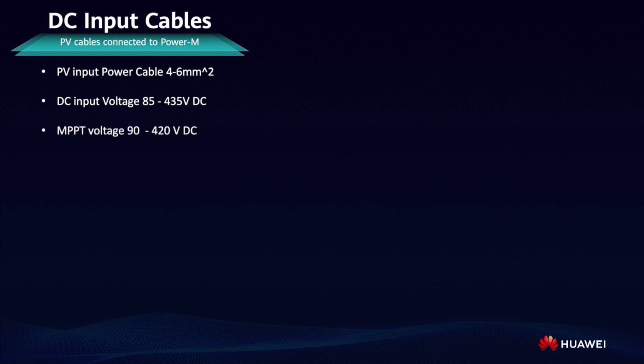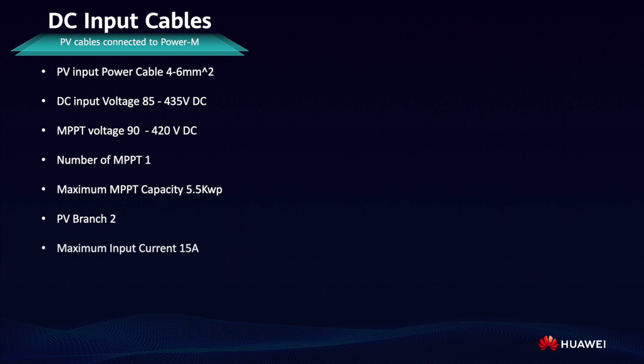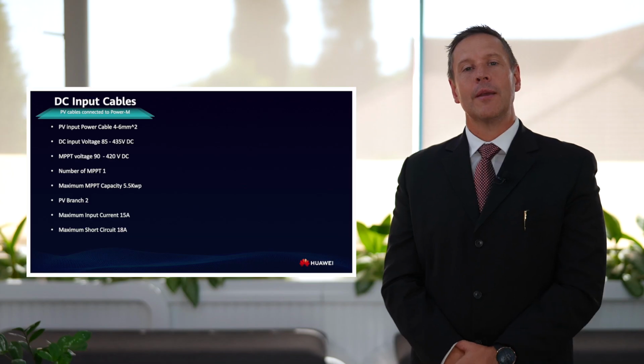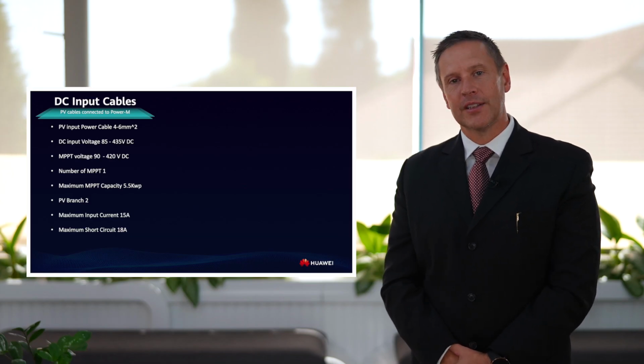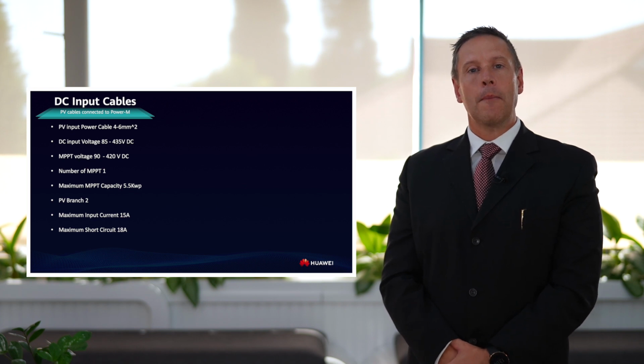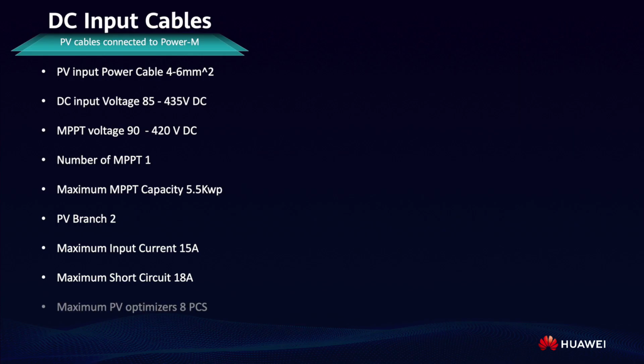MPPT voltage between 90 and 420 volt DC. There's one MPPT on the inverter itself. The maximum MPPT capacity of 5.5 kilowatt must be adhered to. There are 2 PV branches and the maximum input current is 15 amp into each branch, therefore allowing up to 30 amp in the combined configuration. The maximum short circuit is 18 amps. The Power M is also capable of accepting optimizers in order to maximize PV yield that's available from shaded roof structures. The maximum PV optimizers that can be connected is 8 pieces.